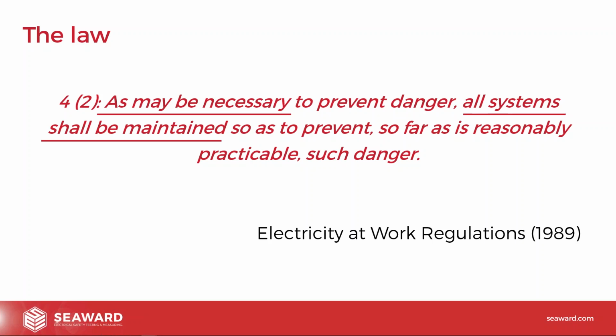So again, how often do we do it? Enough to prevent danger. So from a legal point of view, there's nothing in that that says every 12 months. That's just become, again, a myth, a thing that people have just done. Yeah, we do it every 12 months. Really, it's got to be proportionate to the risk. Now, the other thing is, what does it apply to?